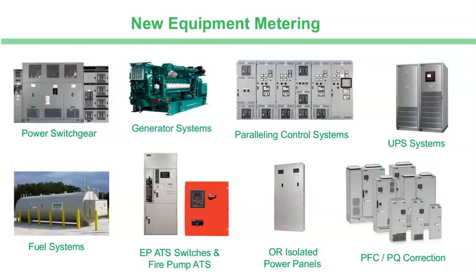Down below, we're showing transfer switches, and again, the OR monitoring panels that I mentioned earlier. Those are ideal places for metering to be incorporated. In fact, in many of the OR panels, the metering communications is normally standard for most of the industry providers. On the far right-hand side, we have UPSs and power factor, power quality correction devices. It's always important to first meter and determine your need for those things, and then based upon that, you can apply the right solution. And then you monitor to make sure it's delivering what you need, to make sure there's no maintenance issues. Certainly if you have power factor correction, for instance, you don't want to find out the unit isn't working properly by getting a high bill the next month. You want to know in real time whether or not it's solving your problems, and all of that is doable.